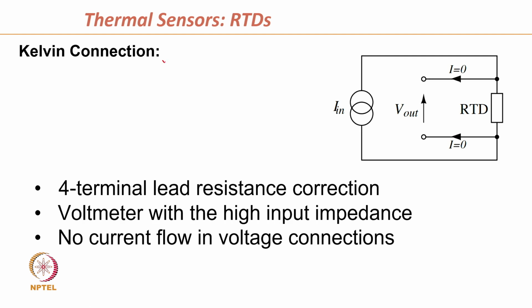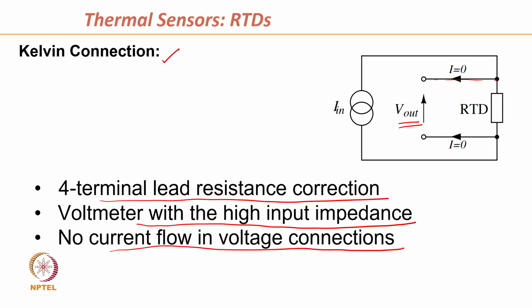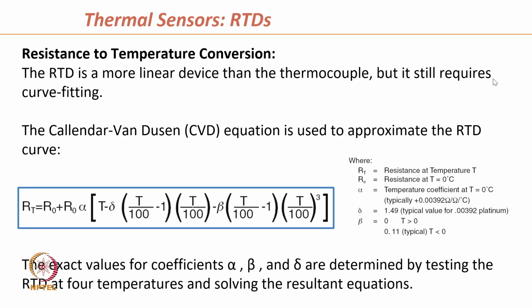and this is the Kelvin connection we generally use in RTD measurement. So, we have this RTD element, we excite this externally, and across this we measure the voltage V out, and we measure the resistance of these RTDs. So, this is 4-terminal lead resistance correction, and the voltmeter we use has high input impedance, and no current flows in the voltage connections. This current is very negligible, or we can write 0. Because of this, there is no problem of contact resistance.